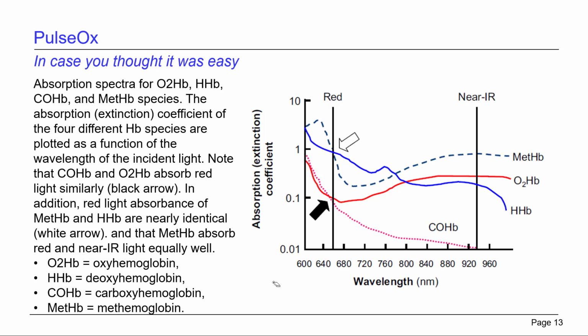Again, just in case you thought things were easy, we actually have 4 different types of hemoglobin. We've got the oxyhemoglobin, deoxyhemoglobin, carboxyhemoglobin, that's the carbon monoxide that's attached, and then the methemoglobin, which relates more to the iron content. But basically, there's different absorption spectra, as we talked about. The coefficients are different. This coefficient on the y-axis, we say absorption and it says extinction coefficient. Extinction is kind of an odd word in this case, where it's more of an umbrella term, which includes the diffuse nature of the light and that which is absorbed. So it's a little bit more comprehensive. Actually, I should have just struck that out altogether.